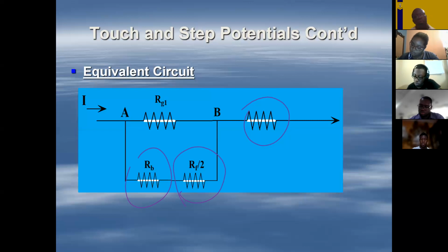But don't focus too heavily on this. We're not going to ask you to do circuit analysis on this. What we're more interested in is how to determine what is that tolerable current, and by extension what we refer to as the touch potential, and the tolerable current when touching equipment during a fault, and the tolerable current while walking around in the substation during a fault.